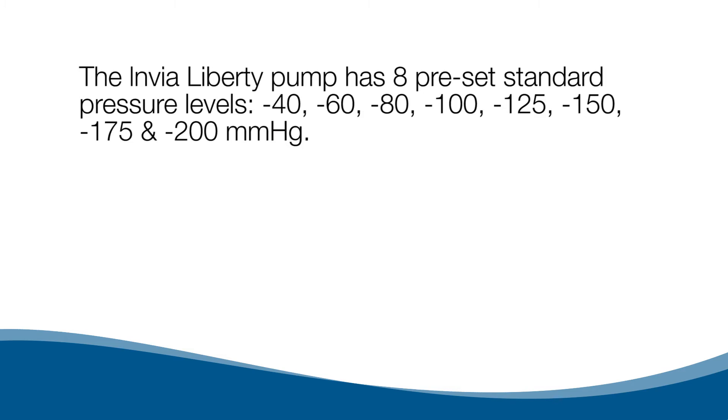The Invia Liberty pump has eight preset standard pressure levels: negative 40, negative 60, negative 80, negative 100, negative 125, negative 150, negative 175, and negative 200 mmHg.